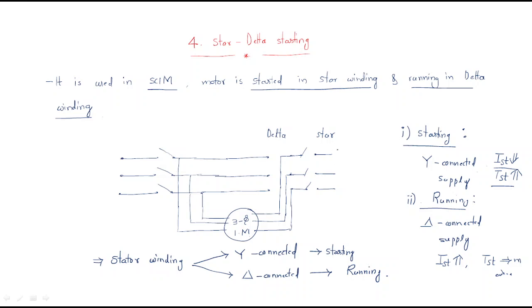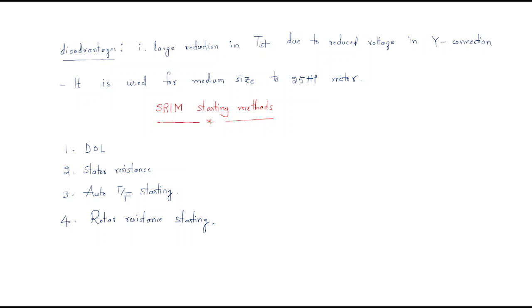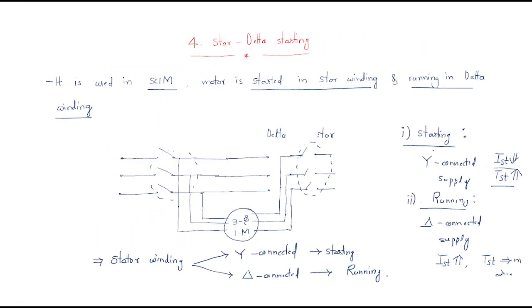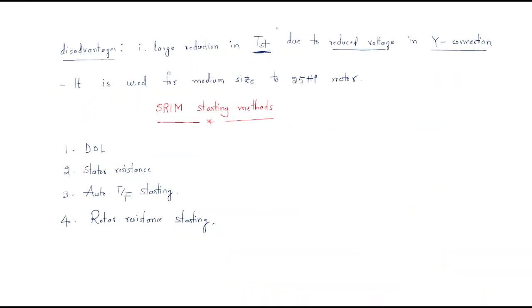This method has some disadvantages. The first is a large reduction in starting torque, because initially a reduced voltage is applied in the star connection system. Due to the reduced voltage, the starting torque will be less. So large reduction in starting torque in the star connection system is the disadvantage.